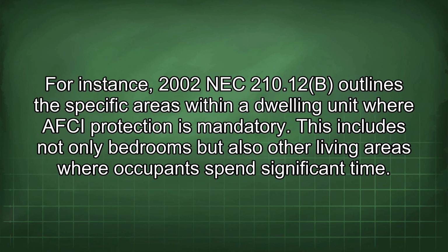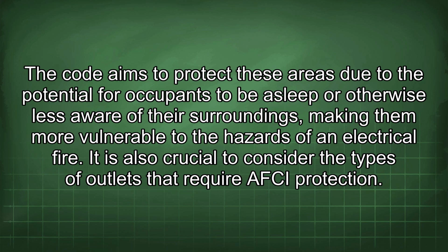For instance, 2002 NEC 210.12(B) outlines the specific areas within a dwelling unit where AFCI protection is mandatory. This includes not only bedrooms but also other living areas where occupants spend significant time. The code aims to protect these areas due to the potential for occupants to be asleep or otherwise less aware of their surroundings, making them more vulnerable to the hazards of an electrical fire.